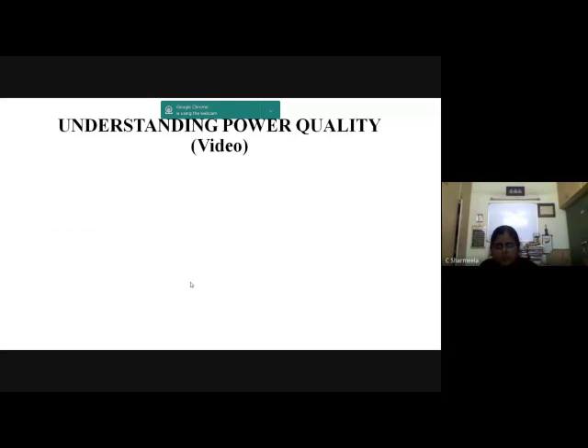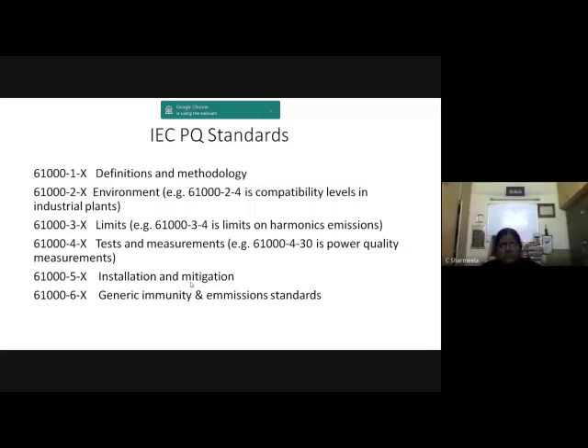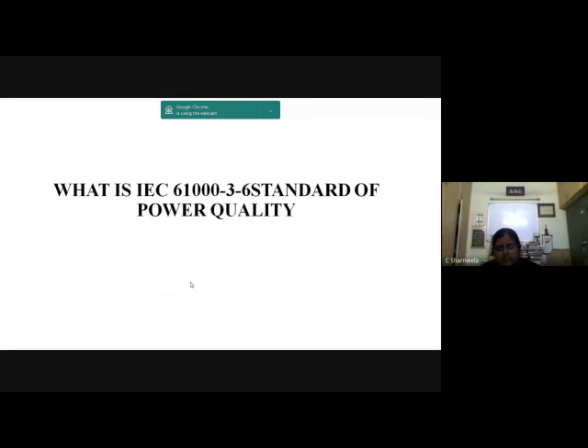There is one more video on power quality, but before going to that, I would like to show you some of the standards for PQ. It starts from IEC 61000-1, where 1 stands for definitions and methodology. It goes up to 6. These things have to be taken care of when you are doing real-time PQ monitoring, and these standards will help in identifying the emission limits for individual equipment connected to the medium voltage and high voltage systems, so that you know the admissible values to be allowed.